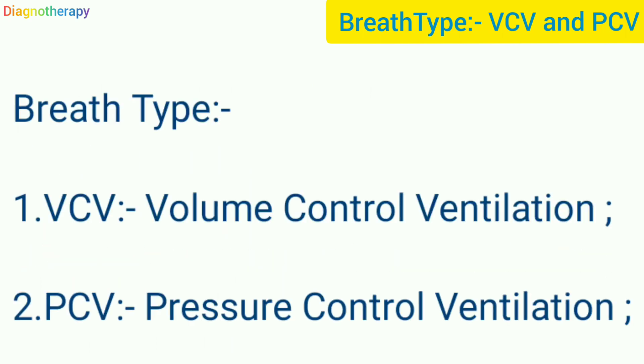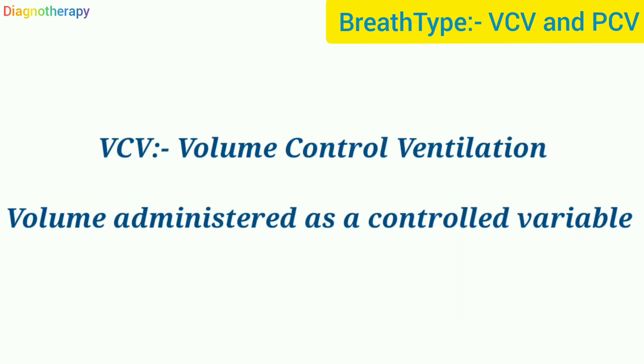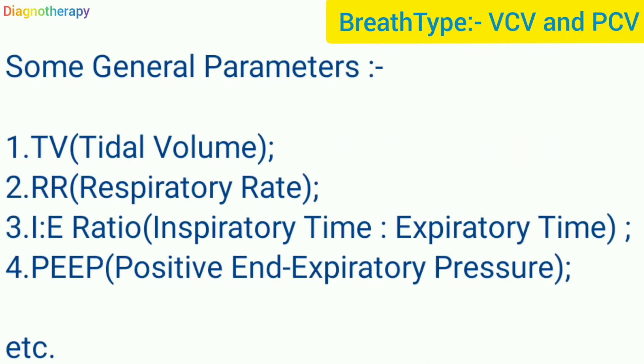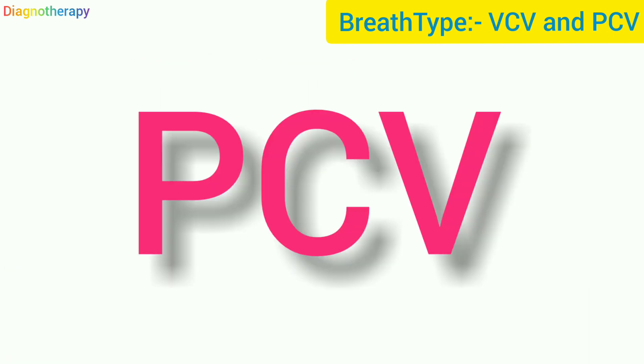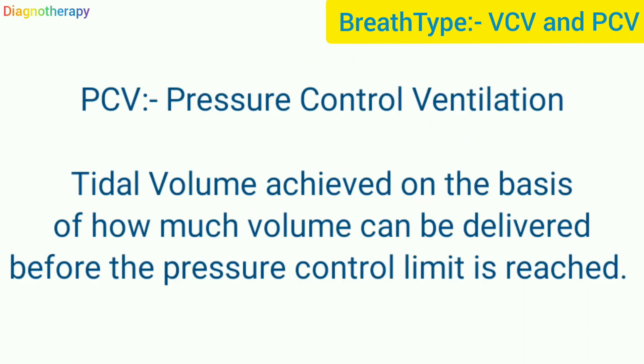In this video we will be concentrating on the breath types: volume control ventilation and pressure control ventilation. In volume control ventilation, volume is administered as a controlled variable. General parameters include tidal volume, respiratory rate, I:E ratio (inspiratory to expiratory time ratio), and PEEP (positive end-expiratory pressure). Different ventilators and models may have slightly different settings.